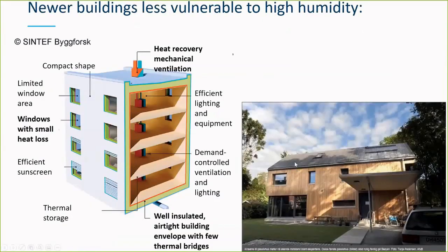Mold fungi are not uncommon and can be rather dramatic. Also the supply air tends to be uncomfortably cold, leading to low ventilation rates because inhabitants close the vents. Newer buildings are a little bit different — they are typically built with very well insulated building envelopes with few thermal bridges, windows with low-e glass, efficient heat recovery and mechanical ventilation, and very importantly an airtight building envelope. So if the indoor humidity gets a little bit high, it doesn't matter because you won't have condensation or mold fungi growing.